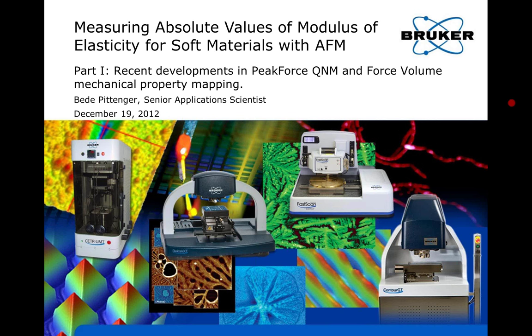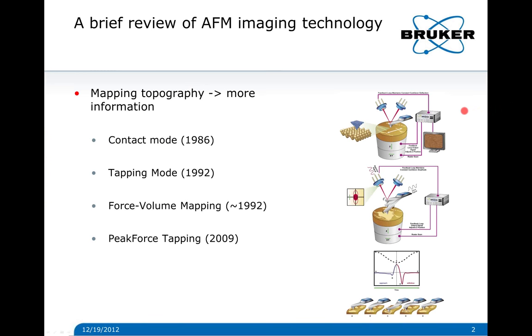Thanks for the introduction, Thomas. I'm Bede Pittenger, and I'll be starting this joint webinar with a review of recent developments in peak force QNM and force volume applied to mechanical property mapping. Let's begin with a review of some basic modes of AFM operation. Contact mode AFM was developed in the mid-80s. The Z position of the piezo was adjusted to keep the cantilever deflection constant while scanning. The downside is that because your tip is always in contact with the surface, the lateral force on the tip is uncontrolled, which could lead to tip and sample damage.